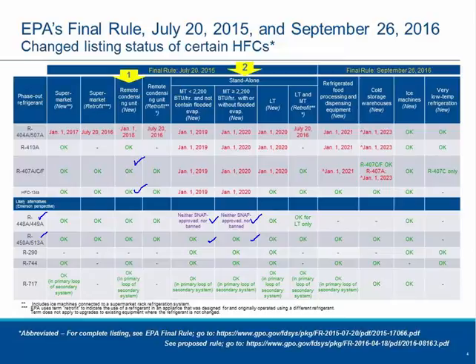We also have propane available that has been SNAP-listed to be used. Propane is an excellent chemical to be used in some of these refrigeration applications. We get improvements in efficiency as well as a boost in capacity. Thermodynamically speaking, it's a great refrigerant. And as you can see in this next column for the low temp side, 448A and 449A are approved for freezers, as well as 450 and 513.